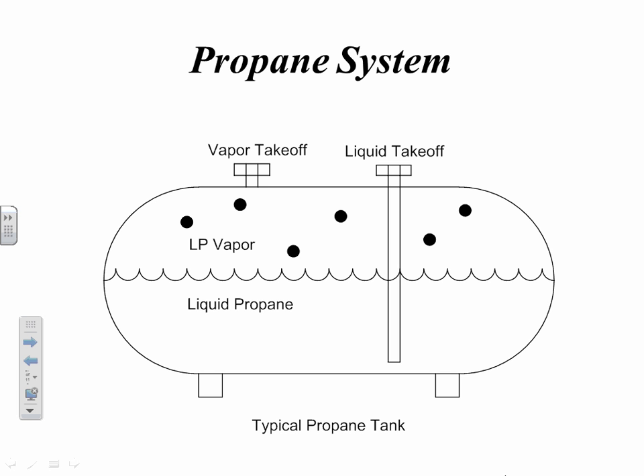So what they do is they take it off as a liquid. This tank is very heavily pressurized. So we'll take the liquid off and run it through an external vaporizer. We've got a water jacket heater on the engine already, so it starts quickly. All generator sets do, whether they're diesel or gas, to make sure they'll start in 10 seconds. So that engine's always warm. We use a little heat exchanger and run this liquid fuel through a primary loop, and it actually gets vaporized by the heat of the water jacket. Then it's pressure reduced through regulators and so on, and then brought into the engine.